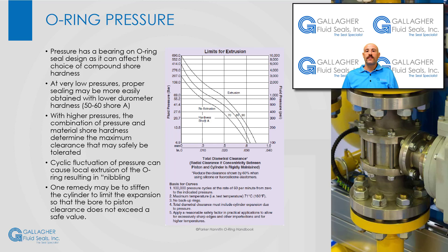Pressure has a bearing on O-ring seal design as it can affect the choice of elastomer hardness. At very low pressures, proper sealing may be more easily obtained with lower durometer hardness, such as 50-60 shore A. With higher pressures, the combination of pressure and material hardness determine the maximum clearance that may safely be tolerated. Cyclic fluctuation of pressure can cause local extrusion of the O-ring, resulting in nibbling, particularly if peak system pressures are high enough to cause expansion of the cylinder wall. One remedy may be to stiffen the cylinder to limit the expansion so that the bore to piston clearance does not exceed a safe value.